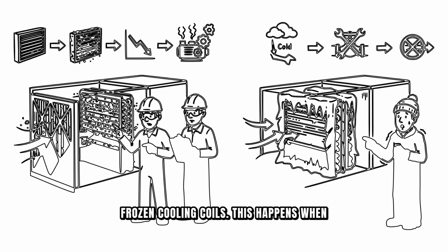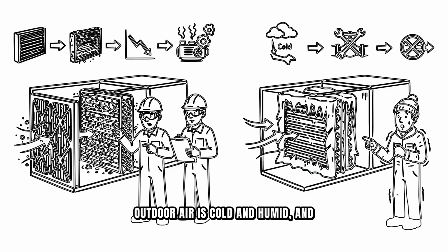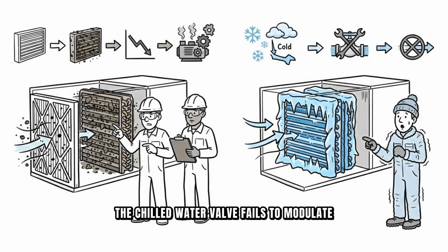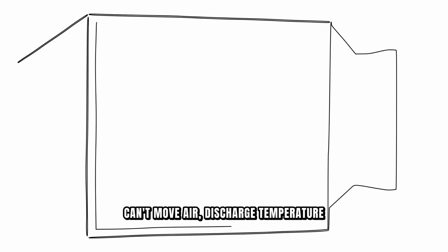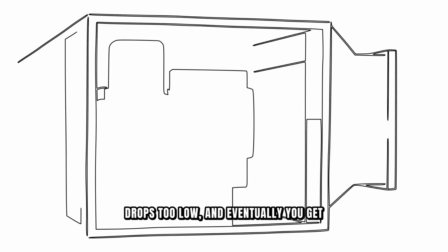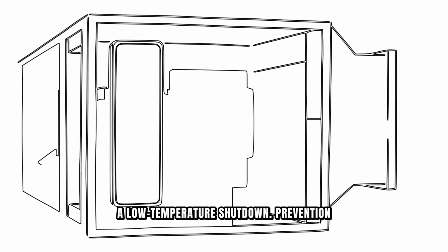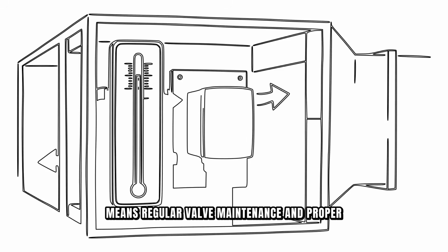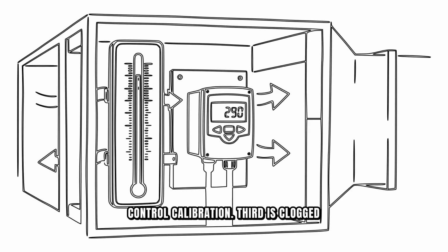Second is frozen cooling coils. This happens when outdoor air is cold and humid and the chilled water valve fails to modulate properly. Ice builds up on the coil, blocking airflow. The system can't move air, discharge temperature drops too low, and eventually you get a low temperature shutdown. Prevention means regular valve maintenance and proper control calibration.